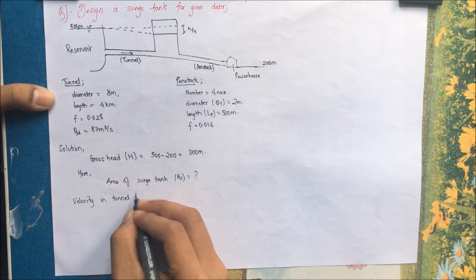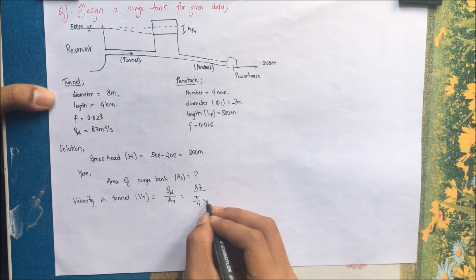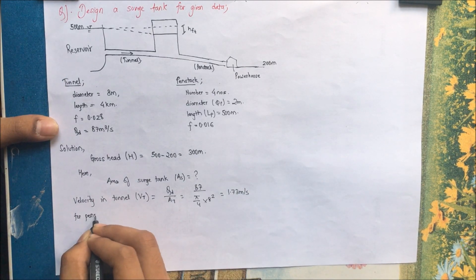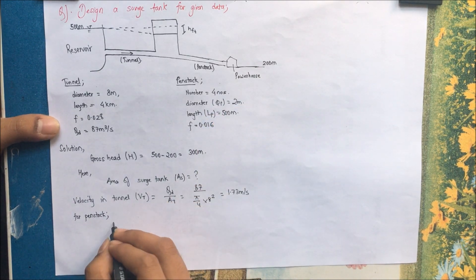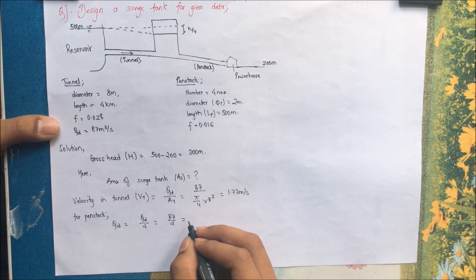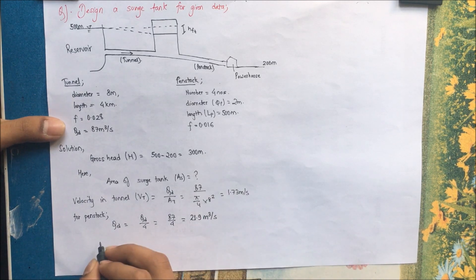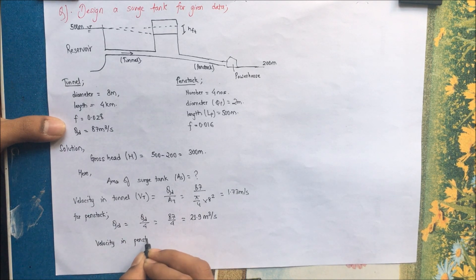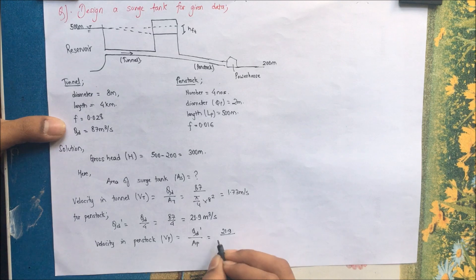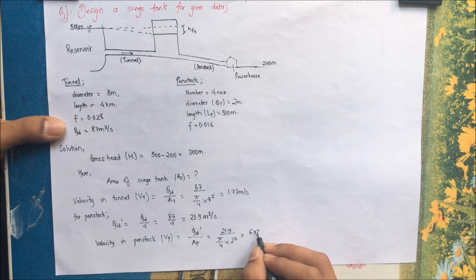Velocity in tunnel: Vt = Qd / At = 87 / (π/4 × 8²) = 1.73 m/s. For the penstock, there are four penstock pipes, so discharge per penstock = 87/4 = 21.9 m³/s. Velocity in each penstock: Vp = 21.9 / (π/4 × 2²) = 6.923 m/s.